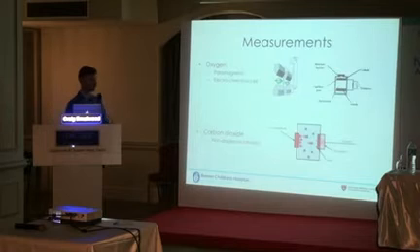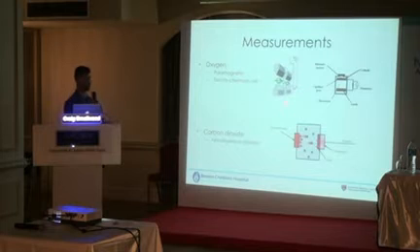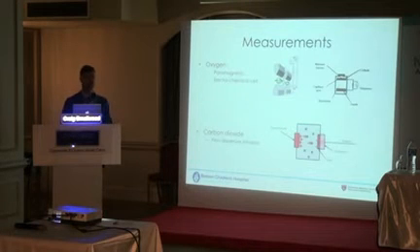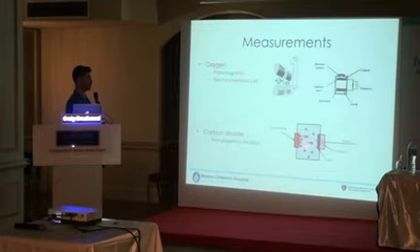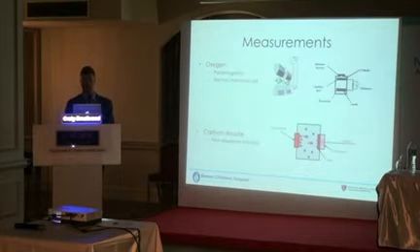The important thing about these different methodologies, this one can be sensitive to motion artifact. So if you're jiggling the device a whole lot, that's usually not a problem. But during transport and stuff, you certainly wouldn't want to apply that one. This one runs out of batteries because it is a battery. And this one is sensitive to like a good window. So if you have water condensation or secretion buildup inside that little monitoring window, then those would be limitations. You'll start to see inaccuracies.